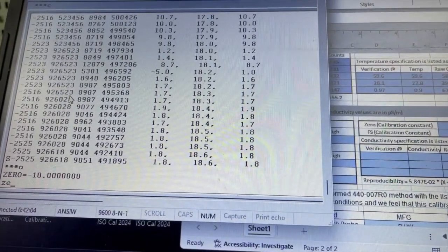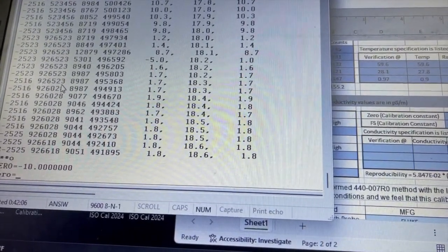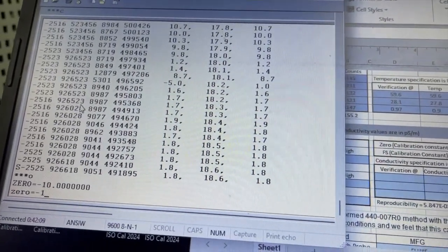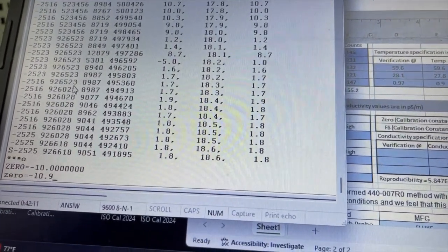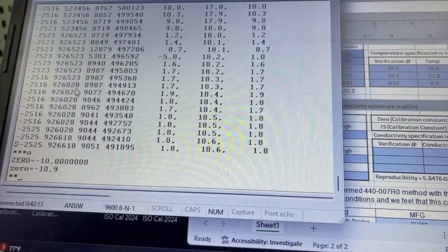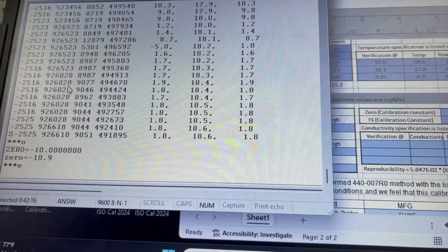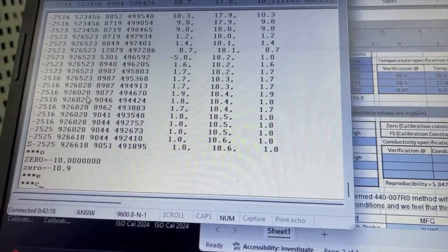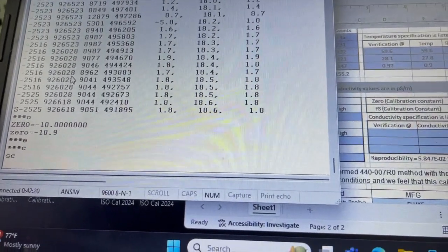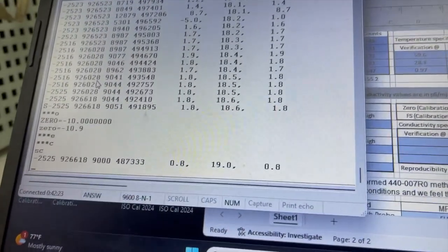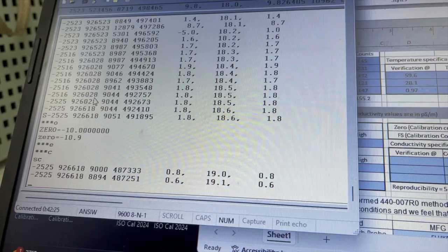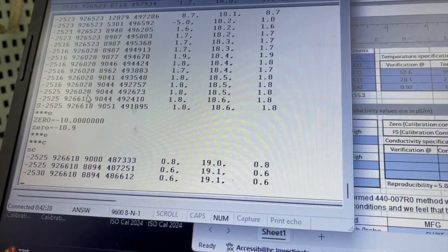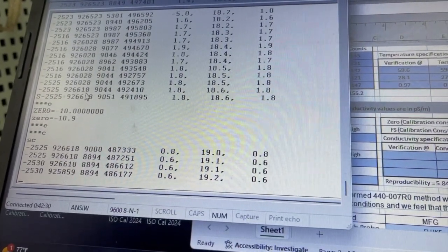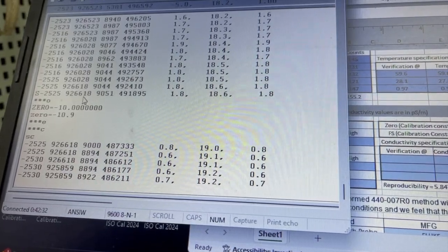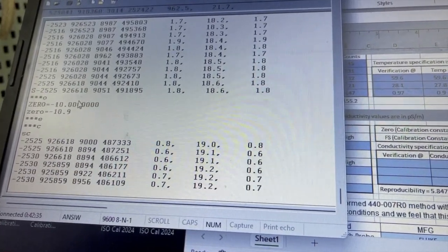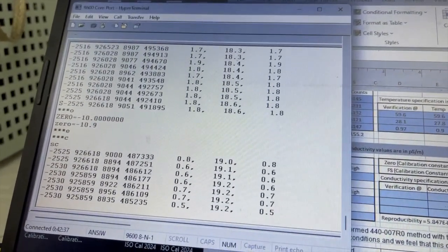So we're going to change the 0 from -10 to -10.9. Save that in the system. And then we will go back into cal mode and check. And now we're getting values right around where we want to be. 0.6, 0.7, 0.7, and we're trying to get 0.9.